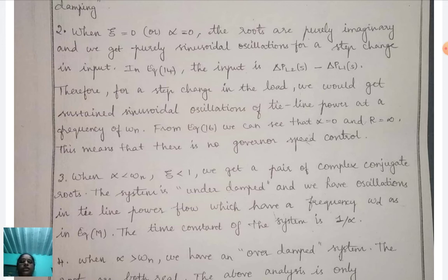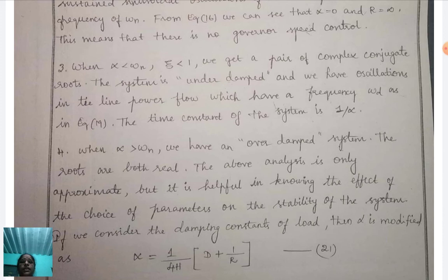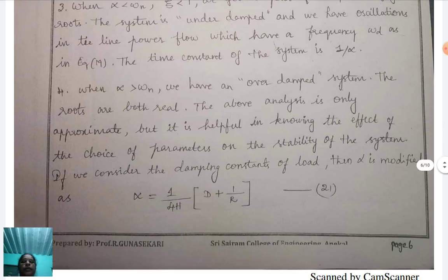In equation 14, the input is del P_L2(s) − del P_L1(s). Therefore, for a step change in load, we would get sustained sinusoidal oscillations of tie-line power at a frequency of ω_N. From equation 16, we see that α = 0 corresponds to R = ∞, meaning there is no governor speed control. When α < ω_N (i.e., ζ < 1), we get a pair of complex conjugate roots — the system is under-damped and oscillations in tie-line power flow occur at frequency ω_D. The time constant of the system is 1/α.